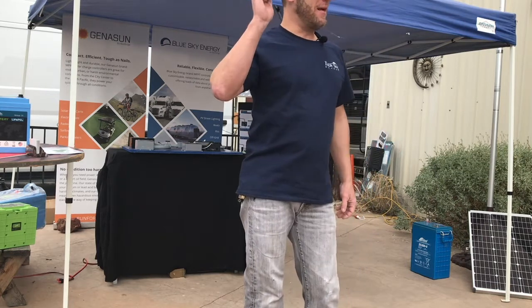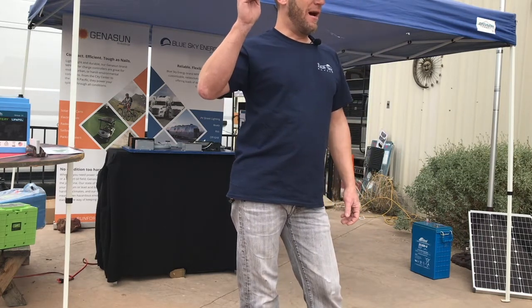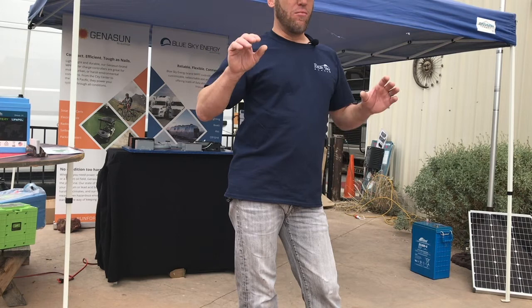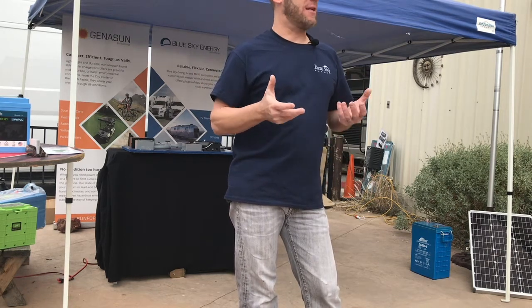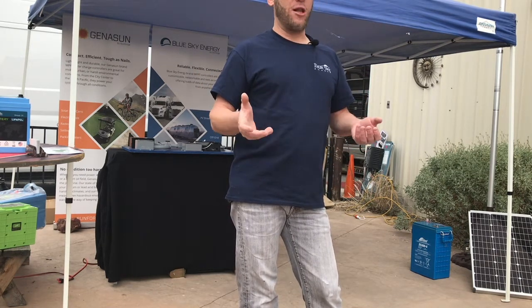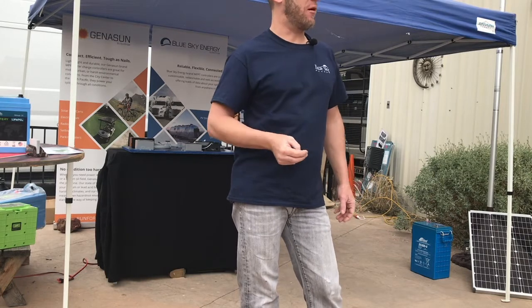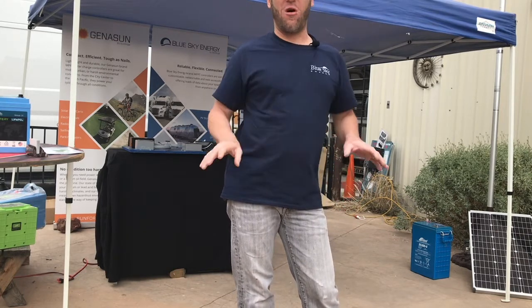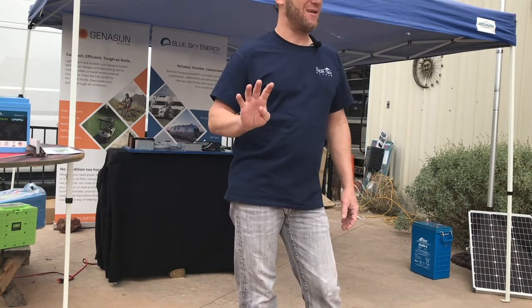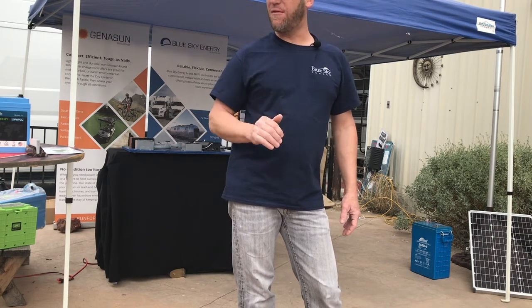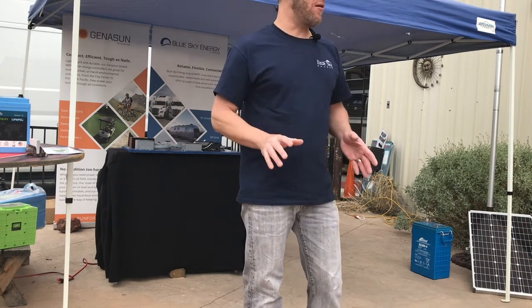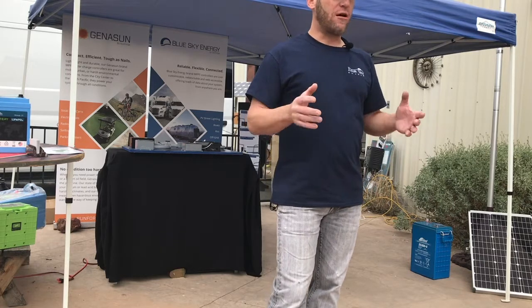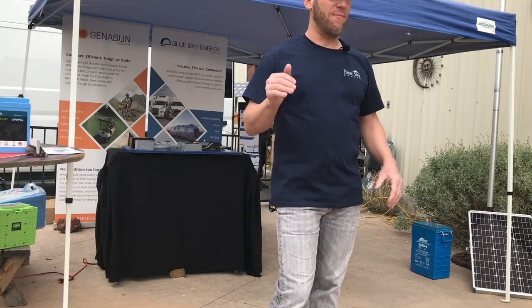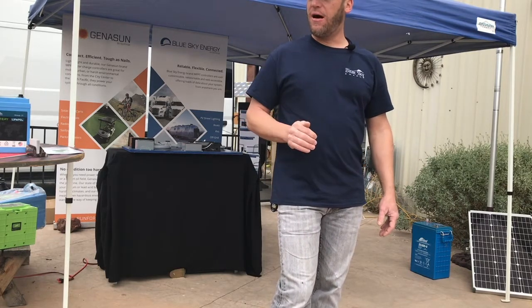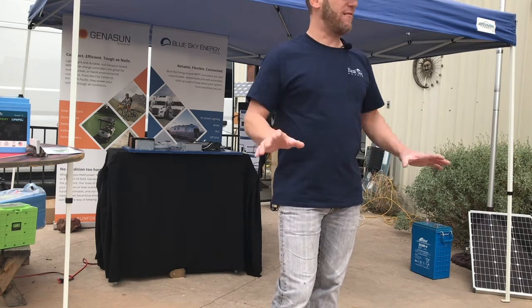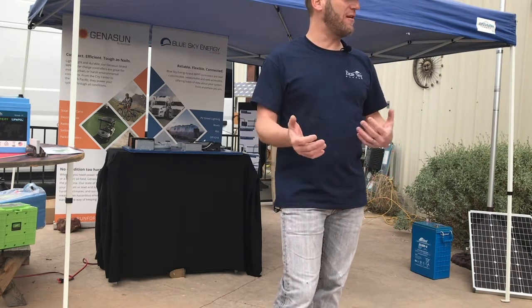So once you maintain the absorption voltage, a standalone charge controller usually bases that on time. If your batteries are fully charged, it might need 2 minutes in absorption. If your batteries have been discharged for a long, long time, it might need 4 hours in the absorption phase. As an industry standard, standalone controllers are usually programmed for about 2 hours of maintaining the absorption voltage. Of course, you can change all these settings on our charge controllers depending on what your usage is.